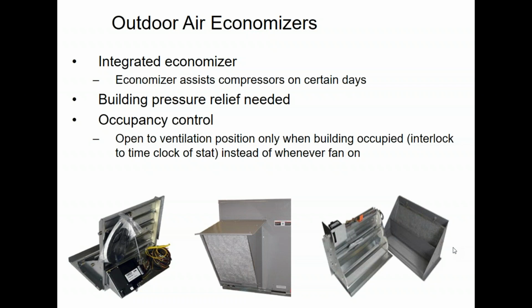But you only bring that outside air in during the occupied time. When the building is unoccupied, you're required by the energy code to shut off that outside air intake. A traditional simple system without DDC controls, for example, like a rooftop with a thermostat, whenever the fan turns on, the outside air damper goes to ventilation position. That's not allowed. We have to stop that from happening. So you either need to have a DDC system that limits that, or you need to have a thermostat that's smart enough to have an additional wire that runs up to the economizer to tell it to shut whenever the building's unoccupied, such as nighttime.